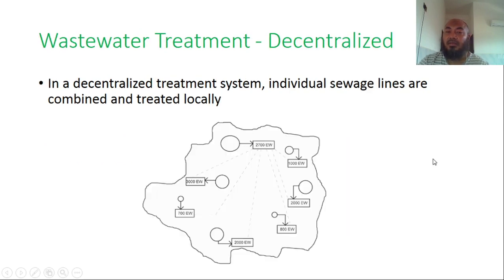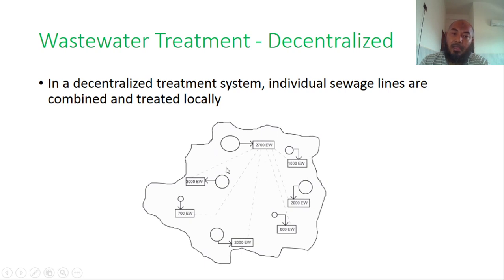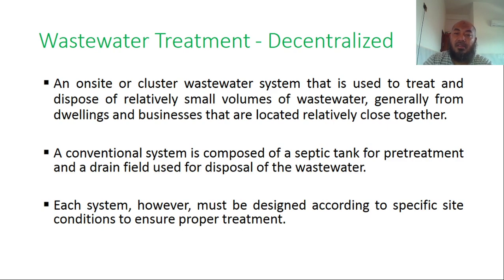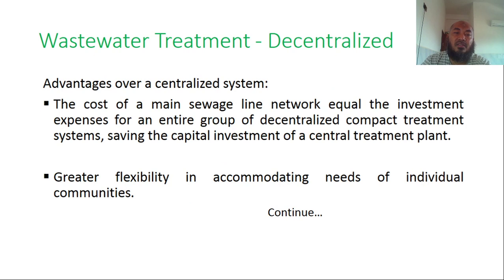In a decentralized system, individual sewage lines are combined and treated locally — on-site or in a cluster wastewater system — used to treat and dispose of relatively small volumes of wastewater generated from dwellings and businesses located relatively close together. A conventional decentralized system is composed of a septic tank for pre-treatment and a drain field for disposal. Each system must be designed according to the specific site conditions to ensure proper treatment.